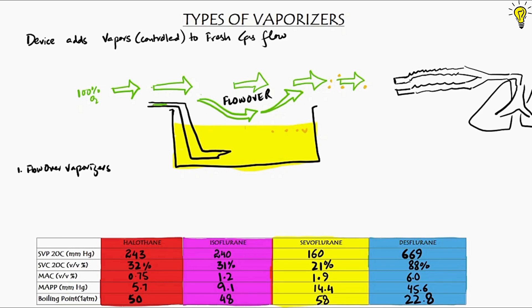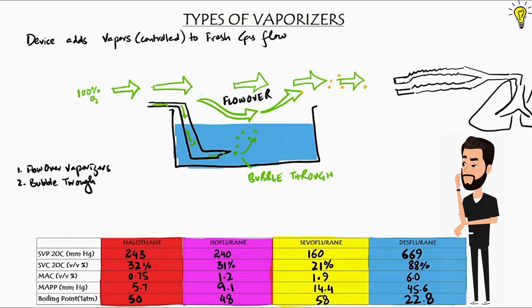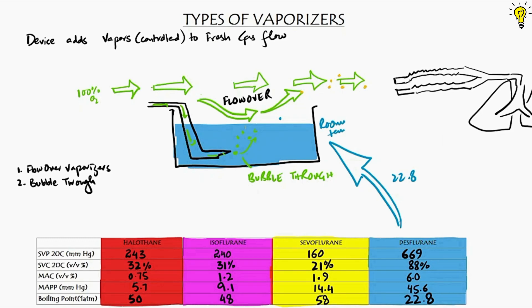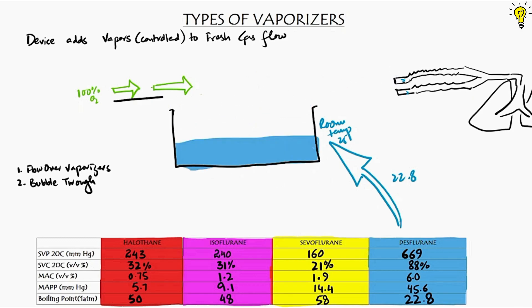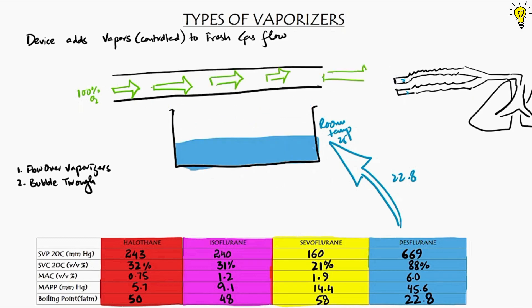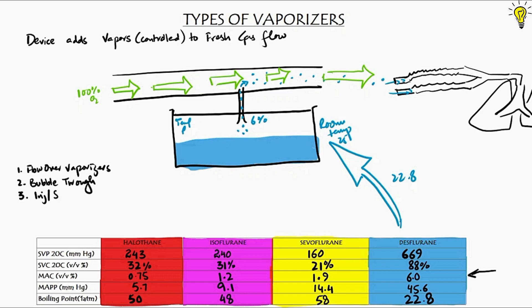Another way to vaporize liquid is via the bubble-through method. But in the case of blue color-coded desflurane, its boiling point is 22.8°C, so it practically boils at room temperature. That means if exposed in flow-over style vaporizers, the saturated vapor pressure would be 100% of 760 mmHg — meaning an overdose going to the patient circuit. So desflurane is contained in a special injection-type vaporizer where fresh gas flows in a separate line and a fixed concentration of desflurane is sprayed into the gas mixture. A fourth kind, the measured flow vaporizer (e.g., halothane copper kettle type), is now obsolete.